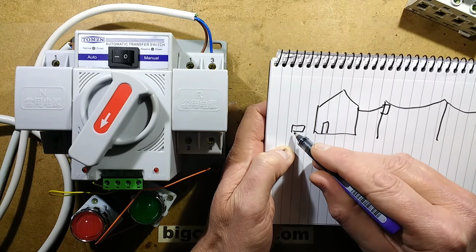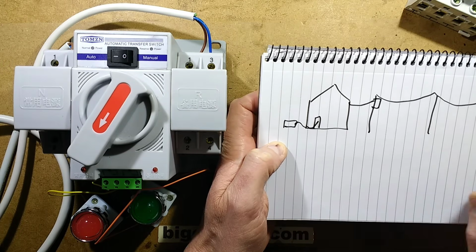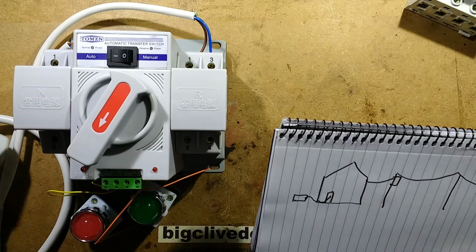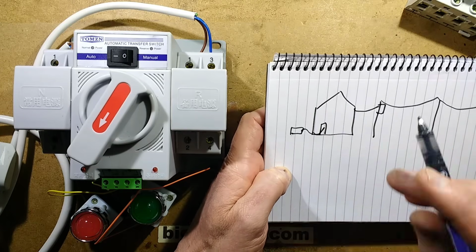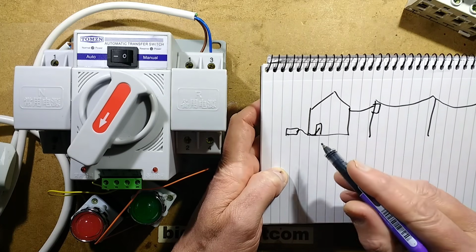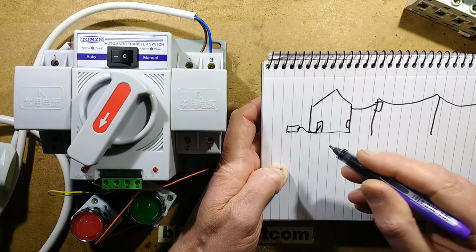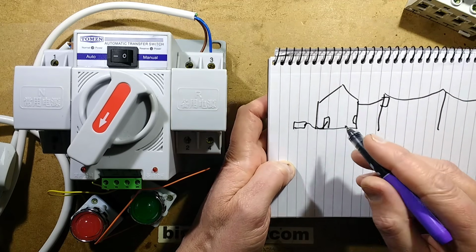But you've got the generator outside, and you have the power cuts, you take a lead into your house, and a really common thing is for people to take dryer leads in, the plug for the outlet for the dryer. And literally on the end of the generator, the live output of the generator, they've got a plug. And that's what we call a widowmaker in the entertainment industry. So you often find these leads that have been made up by people who just didn't know. And the risk there is that if you handle that plug, you're going to get a shock if the generator's running. But what they do is they hopefully turn the power off at their distribution board, and then they backfeed their whole electrical system in the house by plugging that into the dryer outlet in their laundry room, because it's the highest current connector, and it also lets them power both phases in the American system.